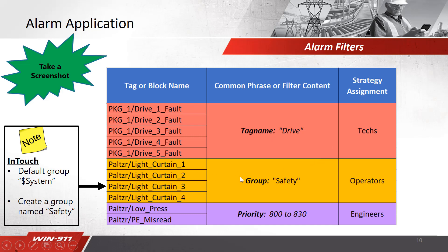The next item: we have palletizer or light curtain alarms that we'd like to go to our operators. I've grouped these in a safety group. One thing to note with InTouch is the default group is the dollar sign system group, but I've created my own group called 'safety'. The last item on the list: a couple of alarms related to the palletizer — misread and low pressure — which we'd like to go to our engineers. These alarms have a priority of 800 to 830.